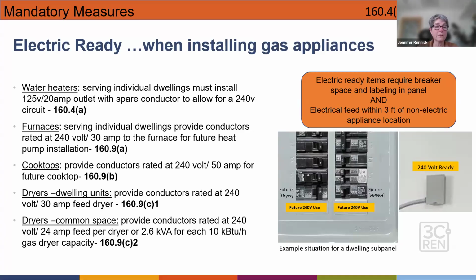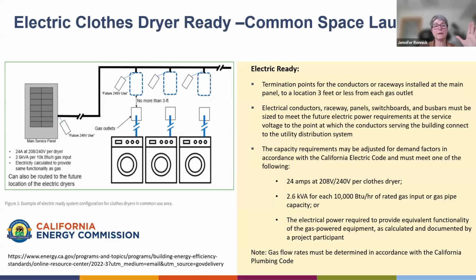Same thing with furnace for space heating, needs to be set up for a heat pump. Cooktops need to be set up for electric. Dryers, both in the dwelling units and the common space, can be gas, but need to be set up for the electrical connection, conduit, and outlets for electric. Each one of those topics has more information and in-depth requirements, but really it only comes into play if you know that you're going to use a gas appliance for any one of those functions.